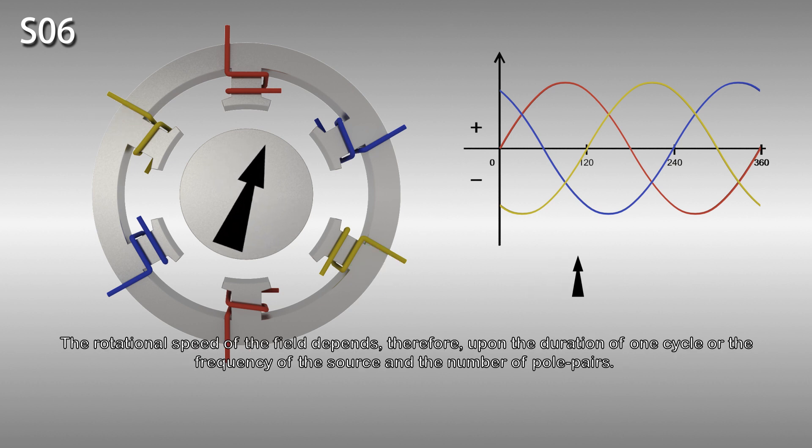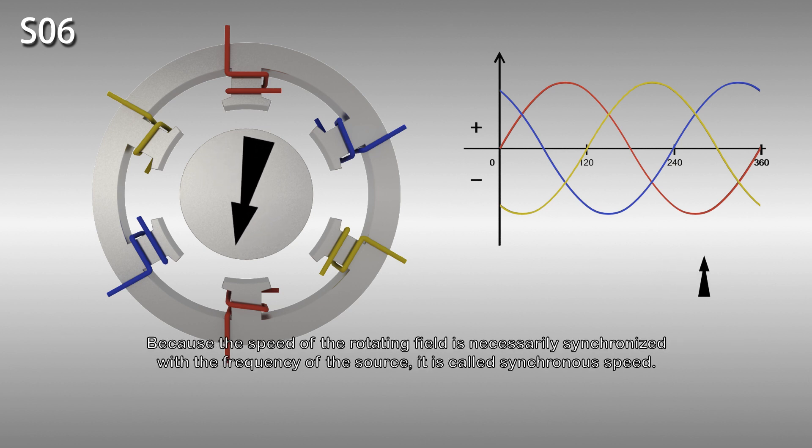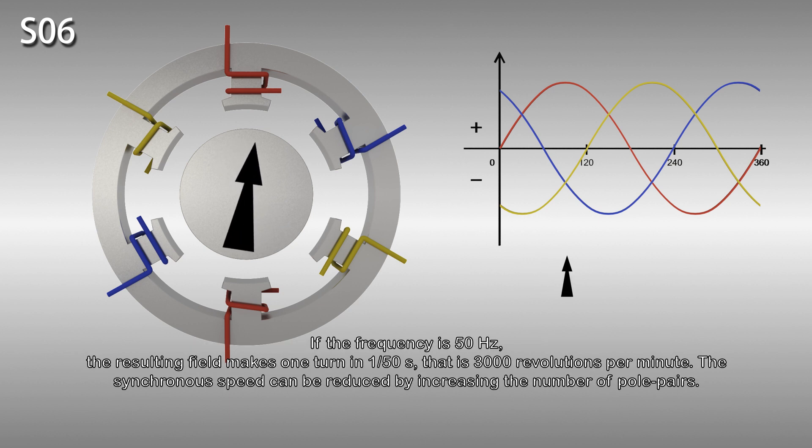The magnetic field rotates with time and makes one complete turn in one cycle of current flow. The rotational speed of the field depends therefore upon the duration of one cycle or the frequency of the source and the number of pole pairs. Because the speed of the rotating field is necessarily synchronized with the frequency of the source, it is called synchronous speed. If the frequency is 50 hertz, the resulting field makes one turn in one fiftieth of a second, that is 3000 revolutions per minute. The synchronous speed can be reduced by increasing the number of pole pairs.